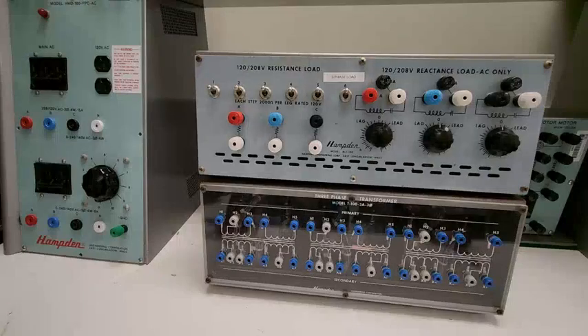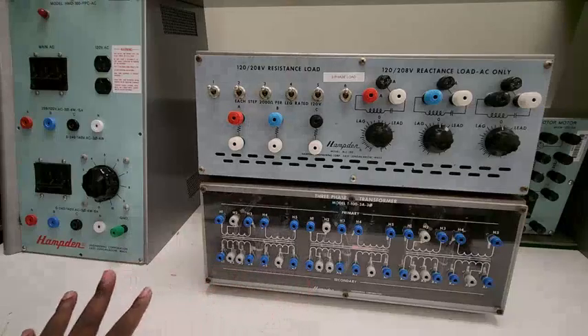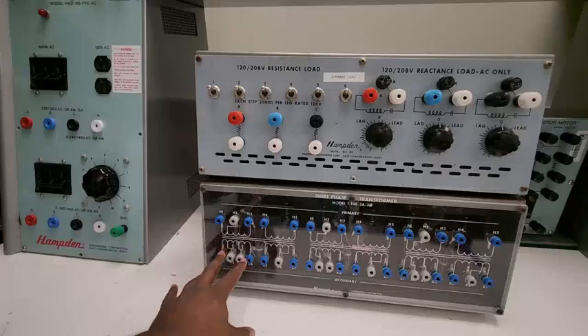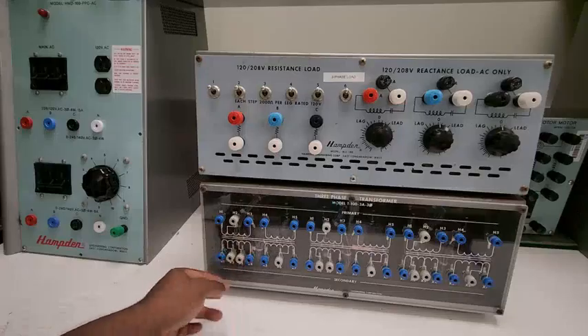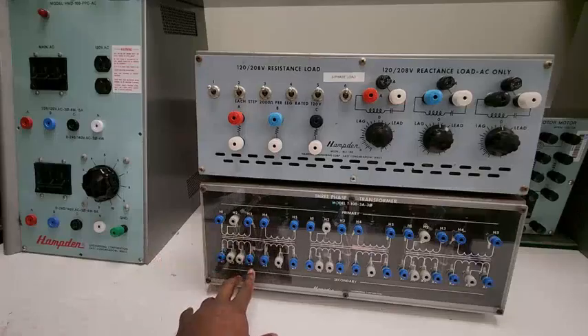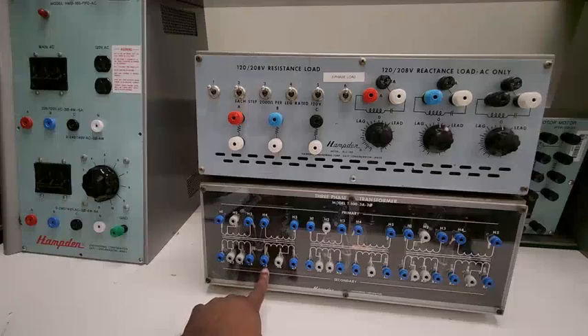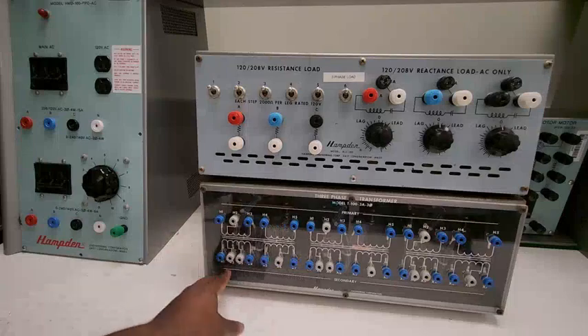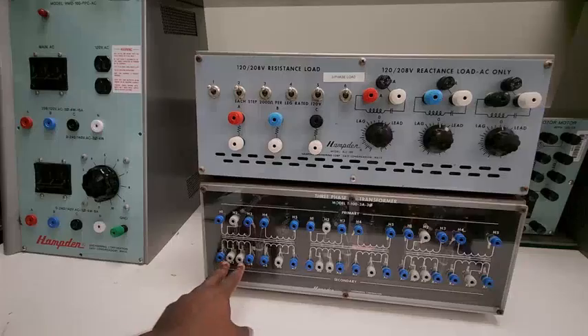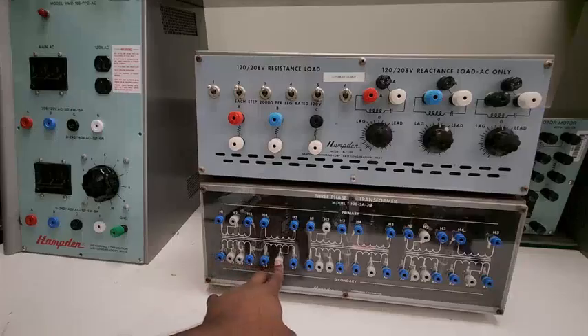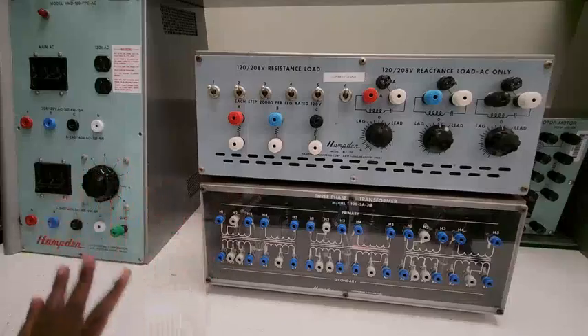Same goes for the secondary side. Although there are many taps, it basically has two large windings. One starts from X1 till X4, and this is X5, with X7 being a separate one. There are taps coming from X1 and X4 — two taps — and one tap coming from X5, X6, X7. These are the names.